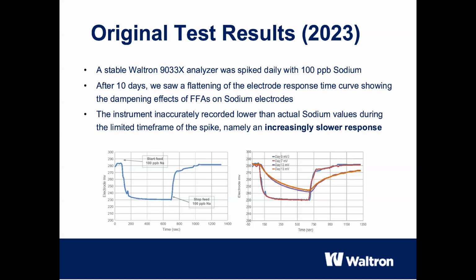After only 10 days of exposure to FFAPs, the response time curve flattened considerably. The device became sluggish and could no longer reach the actual sodium level within the limited time frame. We also observed that the device was falsely indicating lower sodium concentrations than were actually present. This was the first clear indication that FFAs were not only slowing the response time, but actively distorting the measurement itself. These results triggered our more detailed follow-up tests.